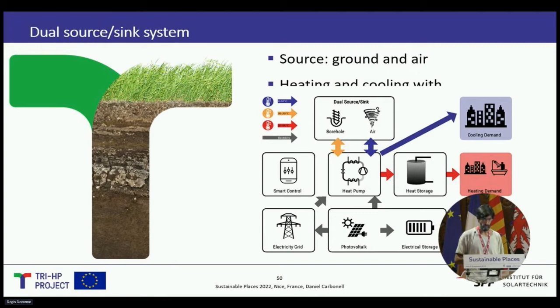It can provide heating and cooling, and this heat exchanger can exchange heat directly with water, groundwater, and air. The aim is to reduce the borehole length by a factor of 2, which will reduce system cost by at least 15%. This system provides heating and cooling, with an advanced energy management system based on model predictive control that decides every 15 minutes the optimal next operation, managing electricity, photovoltaics, battery, household electricity, and heating and cooling demands.